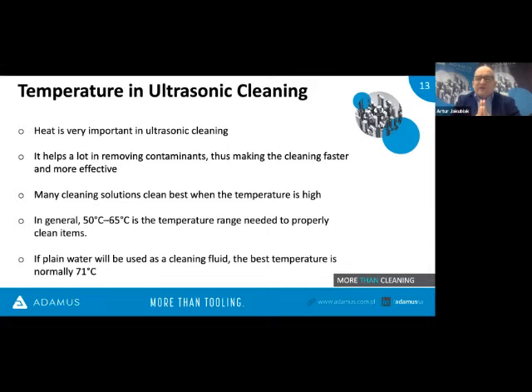What is the importance of the temperature? Well, heat is very important in ultrasonic cleaning because it helps a lot in removing contaminants, thus making the cleaning faster and more effective. Many cleaning solutions clean best when the temperature is high. Generally, the ultrasonic cleaners have a thermostat with which we can regulate the temperature during the process. In general, the temperatures used in ultrasonic cleaners are between 50 and 65 Celsius. And we need this temperature to properly clean items.